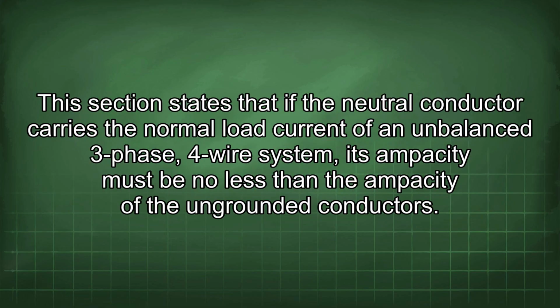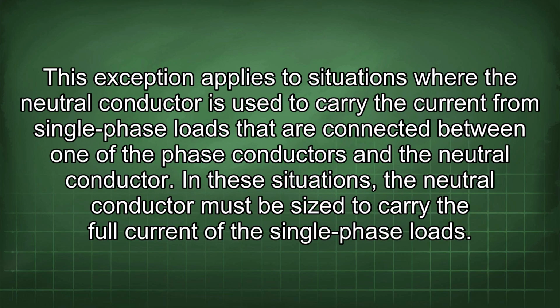This section states that if the neutral conductor carries the normal load current of an unbalanced three-phase, four-wire system, its ampacity must be no less than the ampacity of the ungrounded conductors. This exception applies to situations where the neutral conductor is used to carry the current from single-phase loads that are connected between one of the phase conductors and the neutral conductor. In these situations, the neutral conductor must be sized to carry the full current of the single-phase loads.